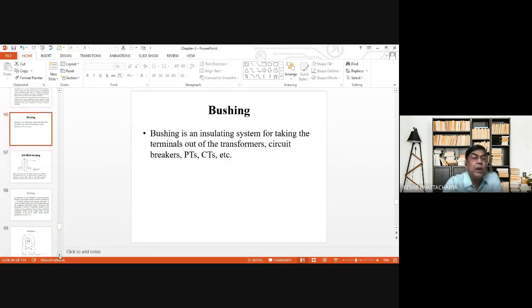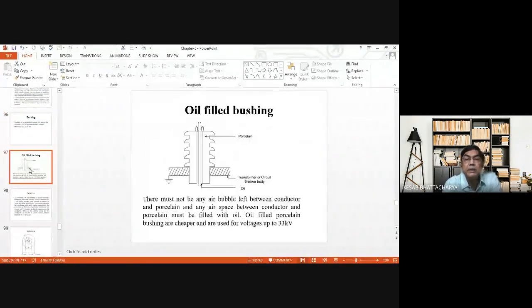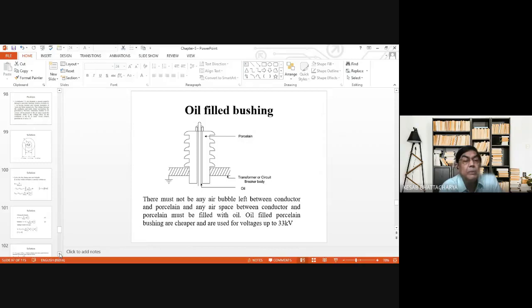Now, the oil filled type of bushing looks like this. You see, this is the flange by which it is connected to the equipment to which a connection is to be brought in or taken out. This is the channel through which oil is circulated, and this is the electrode through which connection is made. This oil is circulated inside just to keep the temperature within limit, so that the bushing remains cool. Again, there are problems which I will not discuss.